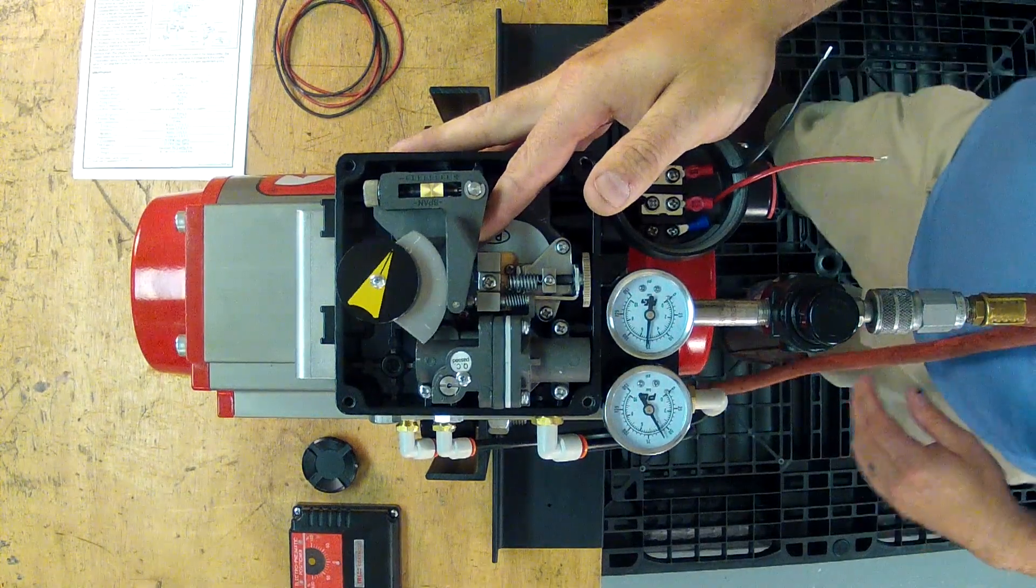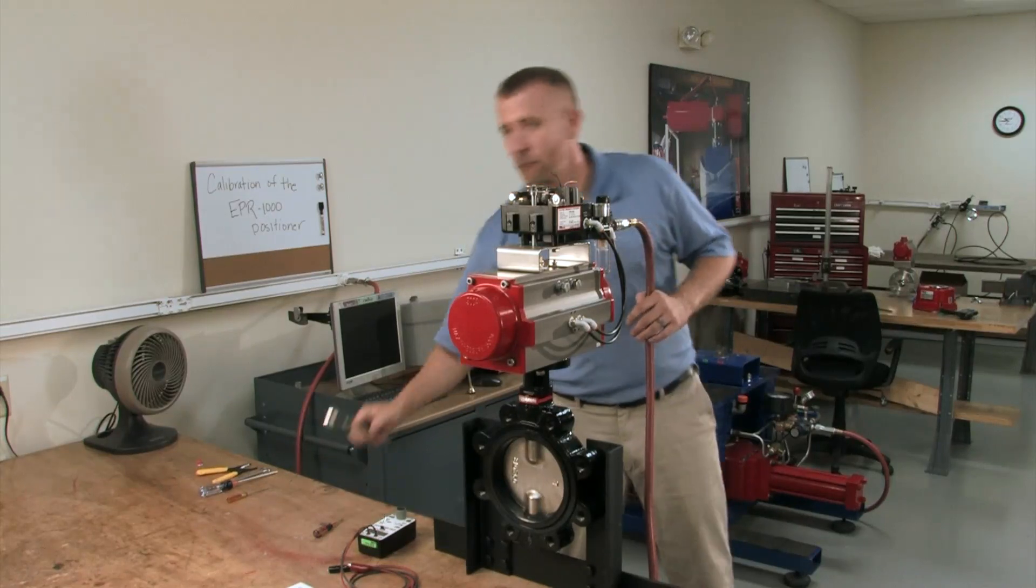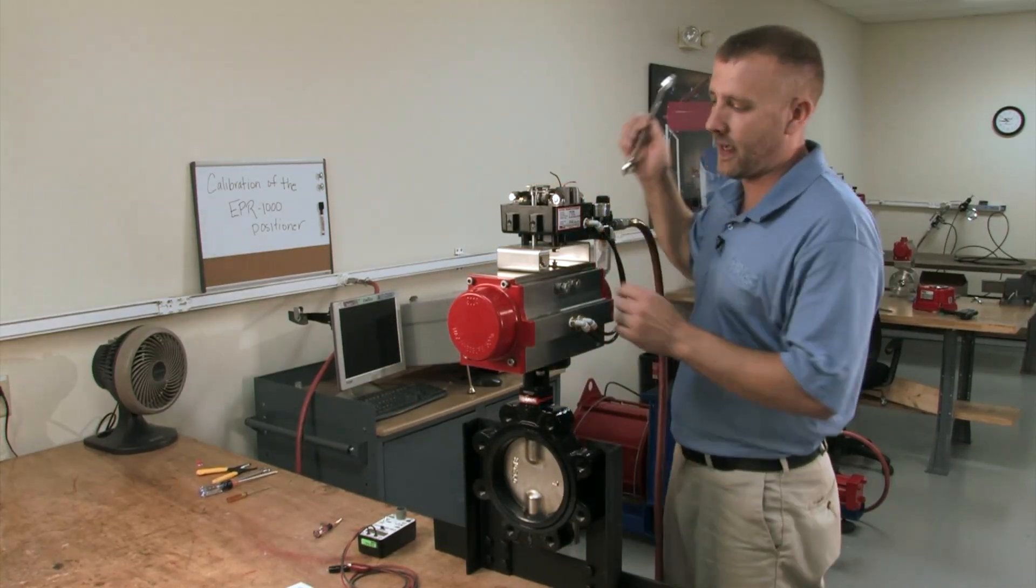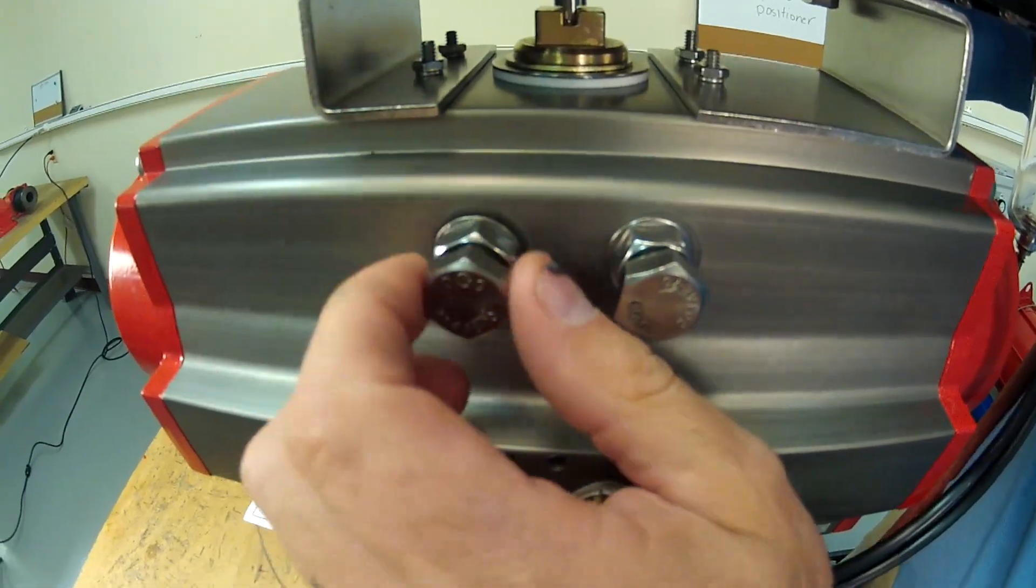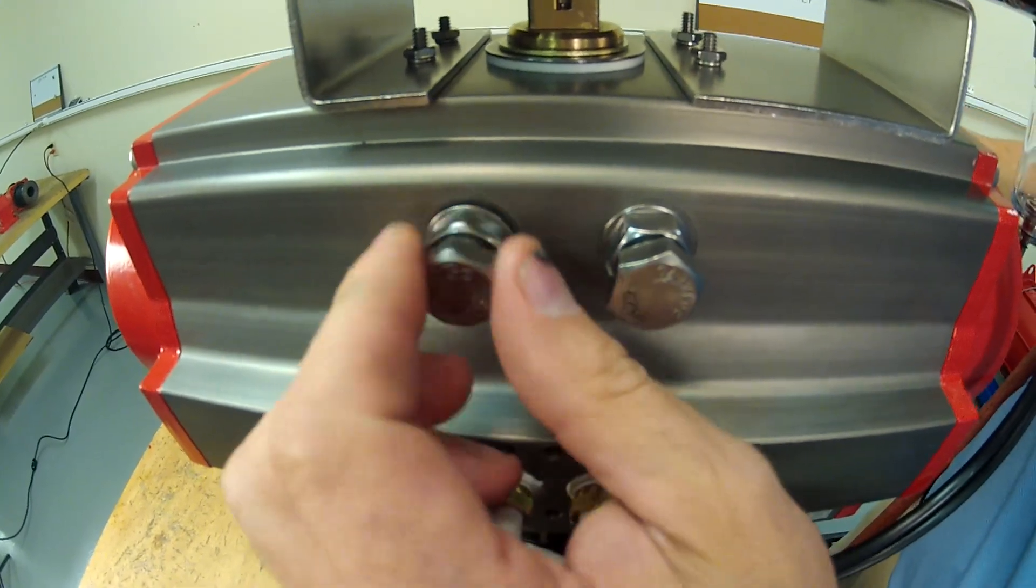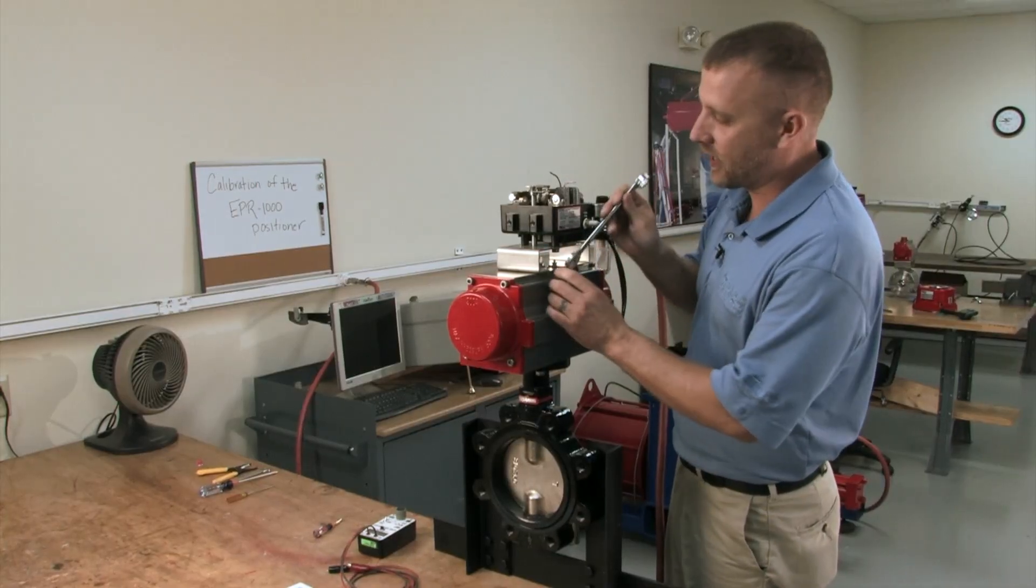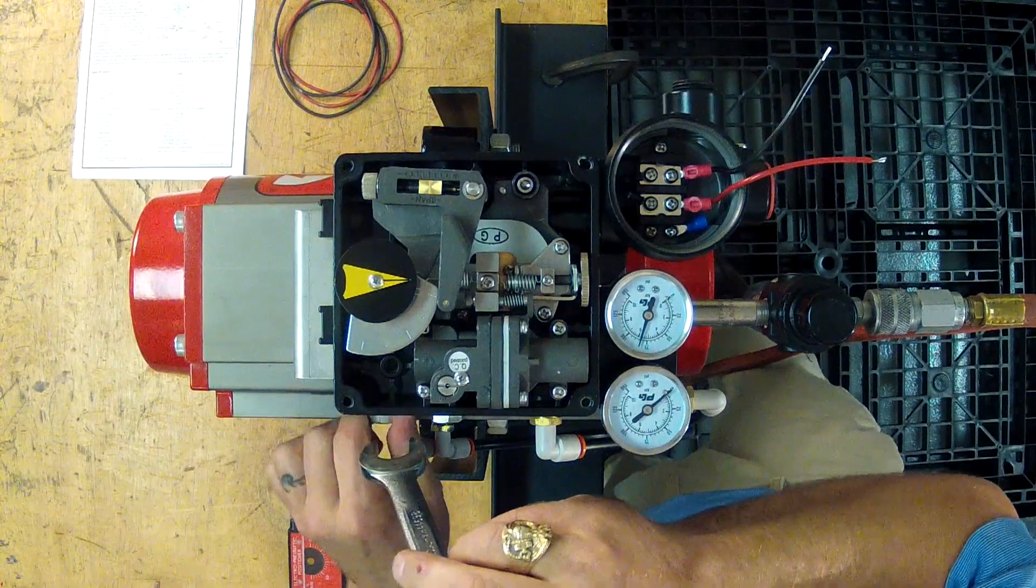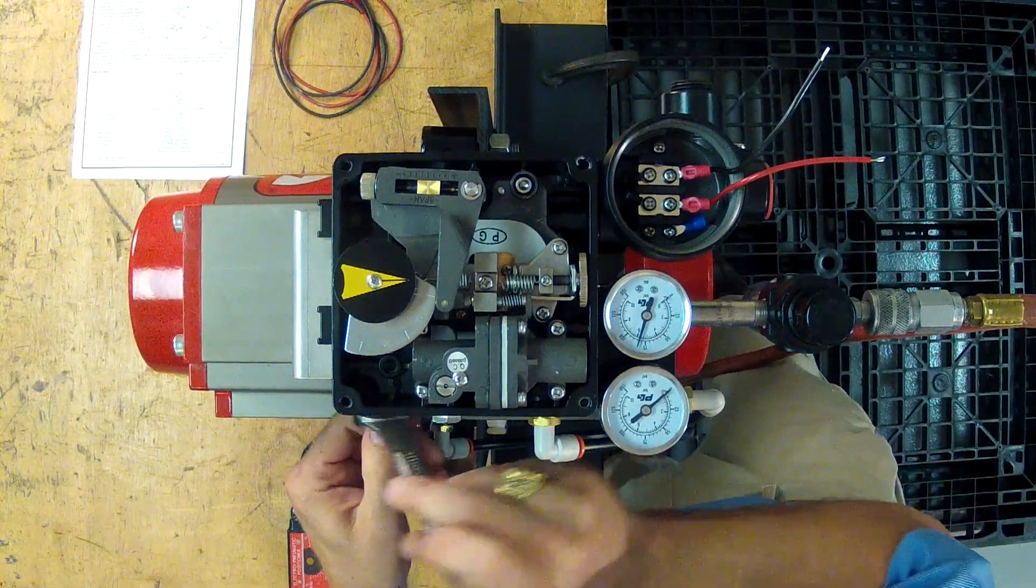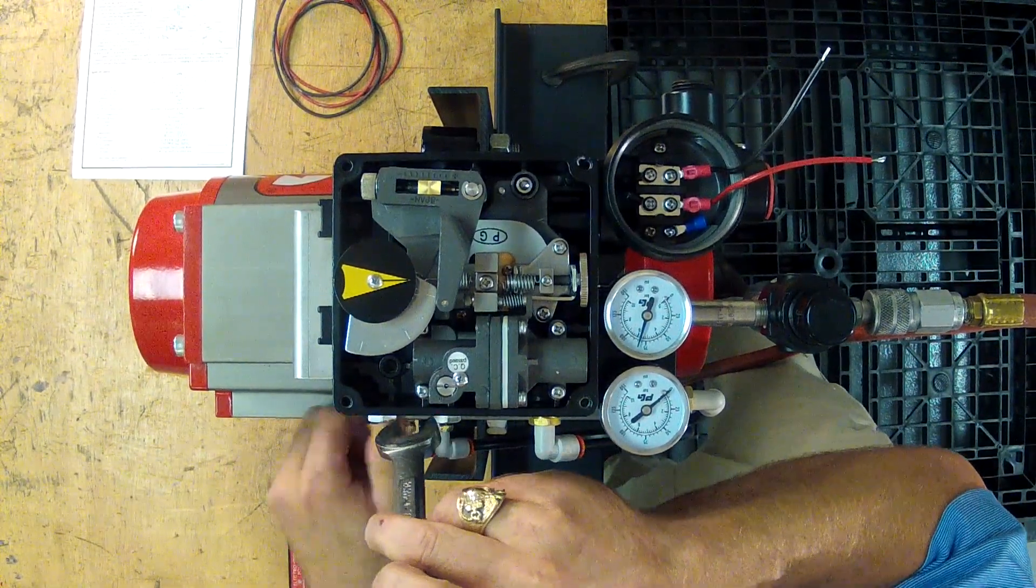But I'm going to demonstrate how to adjust that. Before adjusting your travel stops, you must relieve the spring force that is on your travel stops. This being our open stop, you have five degrees positive and five degrees negative travel on the open and closed stop.